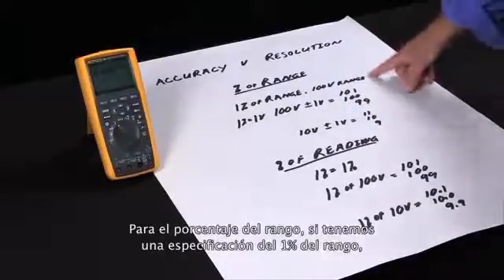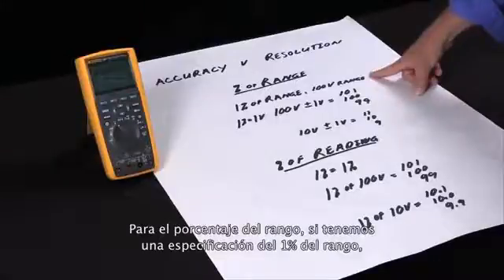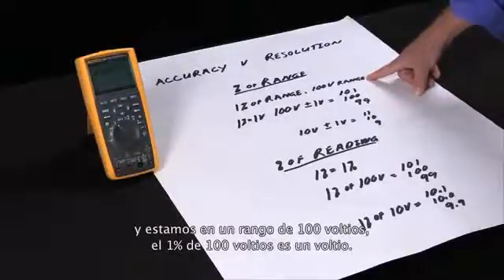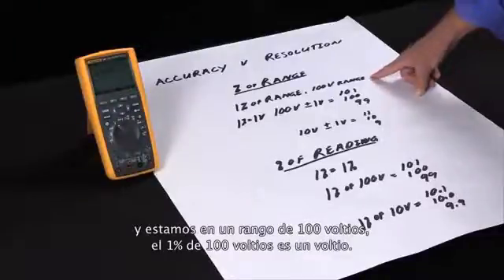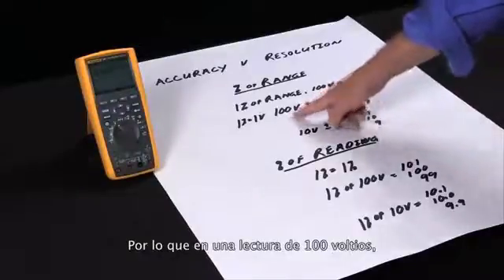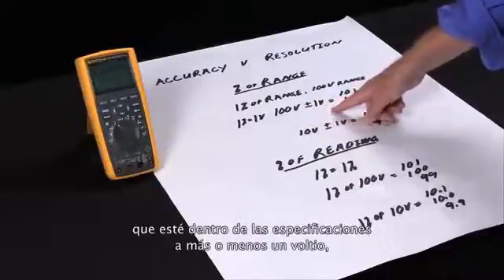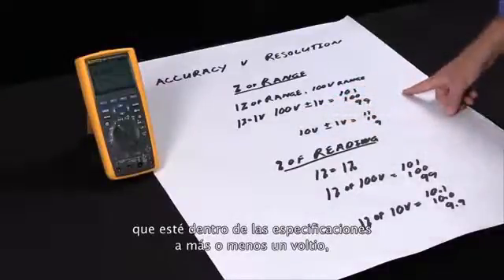For percent of range, if we have a one percent specification of range and we're on a hundred volt range, one percent of a hundred volts is one volt. So that means with a reading of a hundred volts that can be within specification at plus or minus one volt.